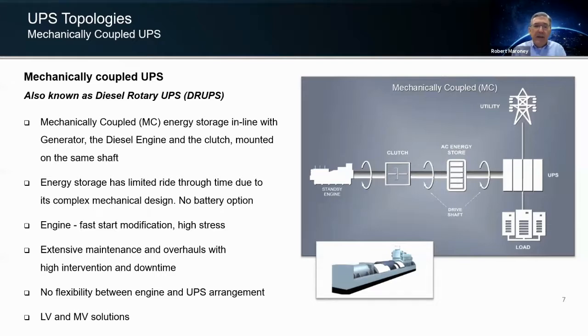It's a lot of maintenance and not very flexible because it all has to be connected in one spot. So in the United States, a lot of people like to put the genset in one location, the UPS in another, and give them more flexibility in that kind of deployment. They are available in not only low voltage, 480 volt, 600 volt, but they're also available in the medium voltage application, which is where you see them a lot as well.